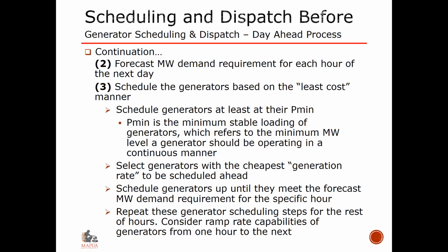That will be impossible for that generator to meet. Aside from starting up, if we neglect other factors such as the startup operation, he cannot reach 0 to 300 in an hour because again, his ramp rate is only 3 megawatts per minute.